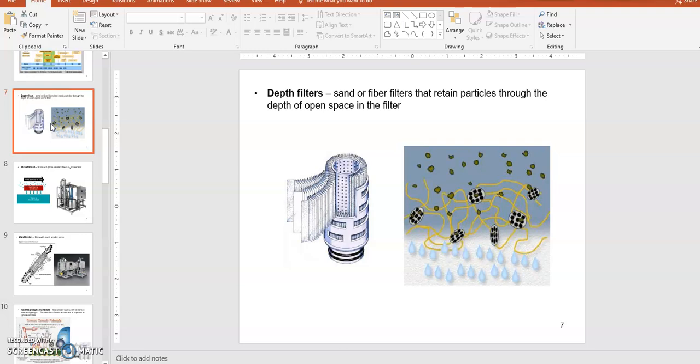When you use a filtration method, filters come in these kind of cassettes. To increase the surface volume, your filter may be folded this way, and your water will run through the filter by running the water through here, pressurized water, and going out. So that's how it works. There are different filter types. Something called depth filter. Depth filter doesn't have really small pores. Instead, they have fiberish materials. These fiber materials can remove large chunky material. So depth filters are used as a pre-filter before your serious filtration.